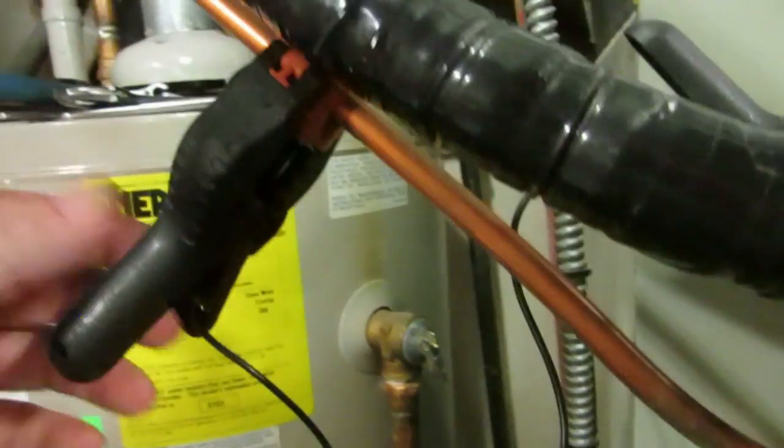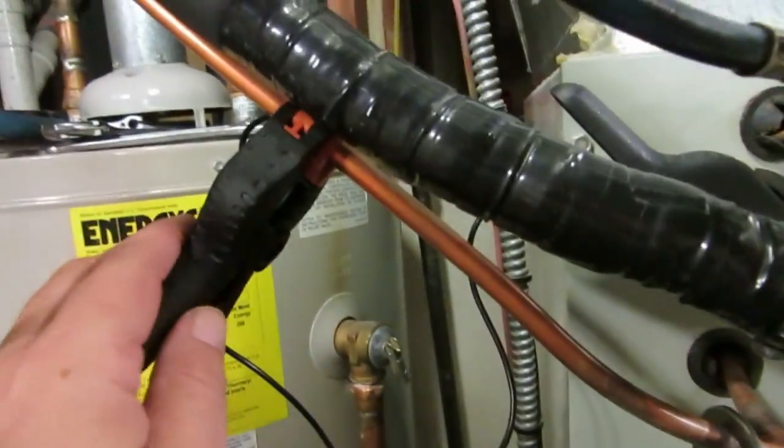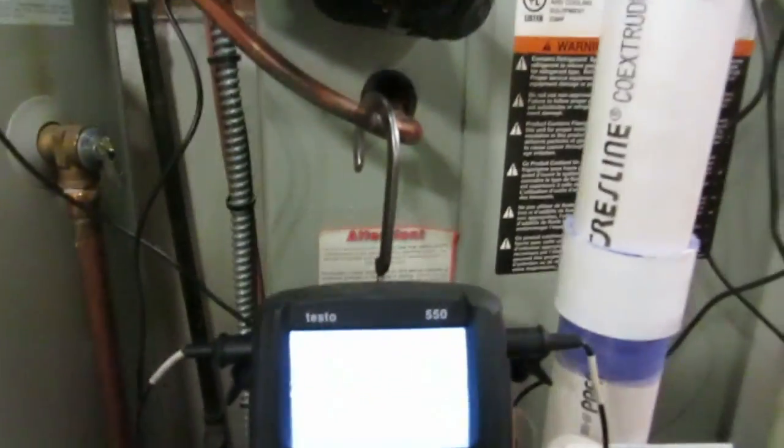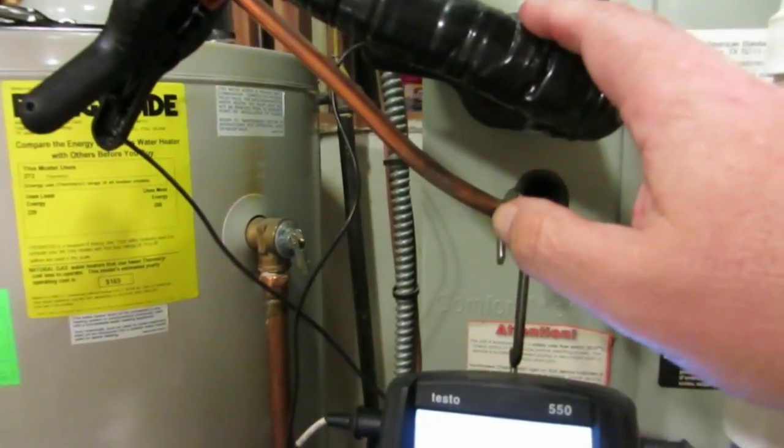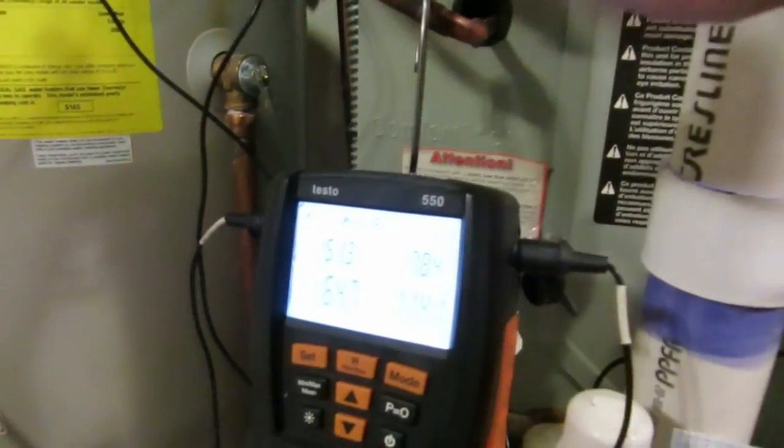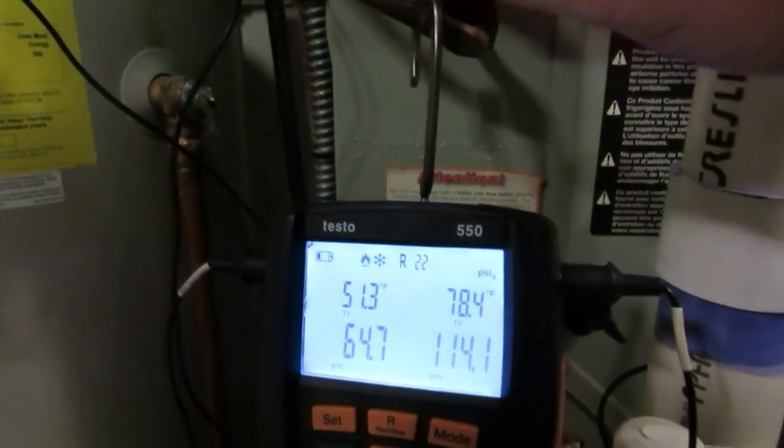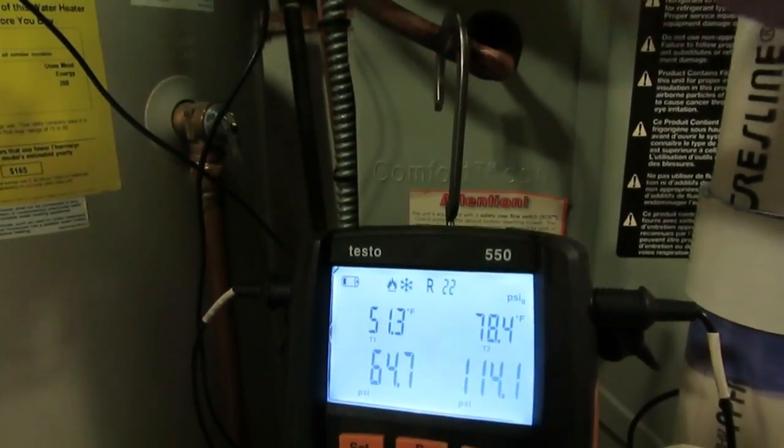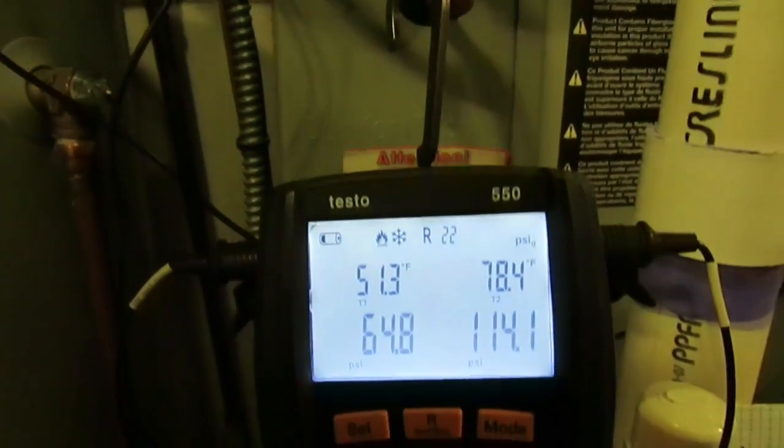Just for giggles, I went ahead and put the liquid side temperature probe on the Testo here. The only reason we did that is because I just wanted to show once again that the Delta T that we're reading on our Testo 550, 557, 570 is actually the temperature differential between T1 and T2, and we'll show you that here in just one second.